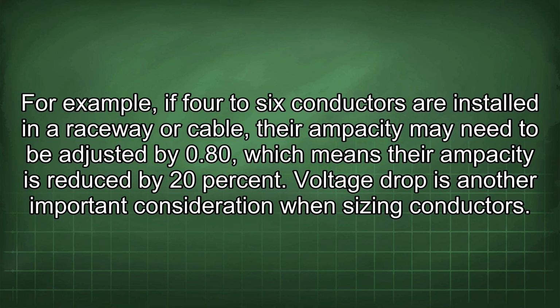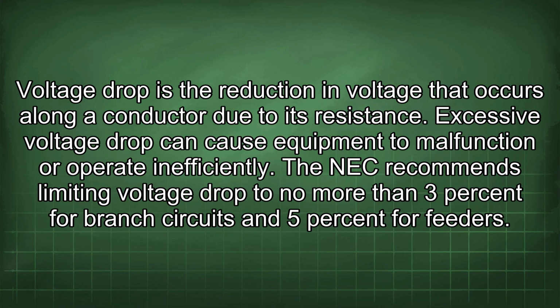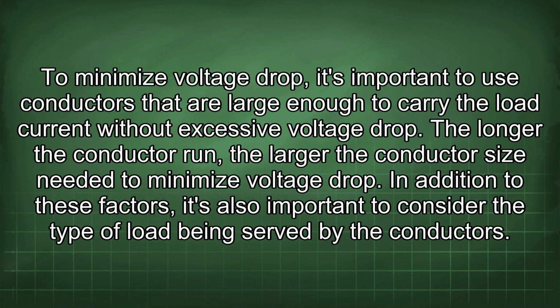Voltage drop is another important consideration when sizing conductors. Voltage drop is the reduction in voltage that occurs along a conductor due to its resistance. Excessive voltage drop can cause equipment to malfunction or operate inefficiently. The NEC recommends limiting voltage drop to no more than 3% for branch circuits and 5% for feeders. To minimize voltage drop, it's important to use conductors that are large enough to carry the load current without excessive voltage drop. The longer the conductor run, the larger the conductor size needed to minimize voltage drop.